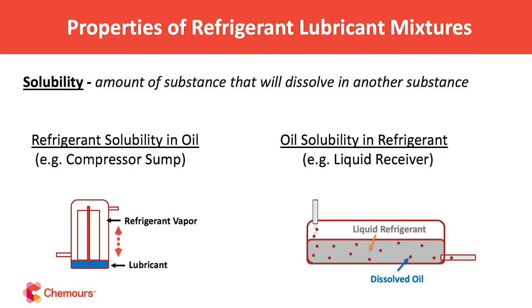Next I want to talk about solubility. The textbook definition is the amount of one substance that can dissolve in another — typically the solvent is the bulk and some smaller amount of solute dissolves into it, like salt in water or sugar in coffee. It's temperature-dependent and depends on the nature of the solute and solvent. Solubility is important in a refrigeration system in several places. From the oil-rich side — in a compressor sump, for example — refrigerant vapor in contact with the oil will dissolve into the lubricant, lowering its viscosity and changing its properties.